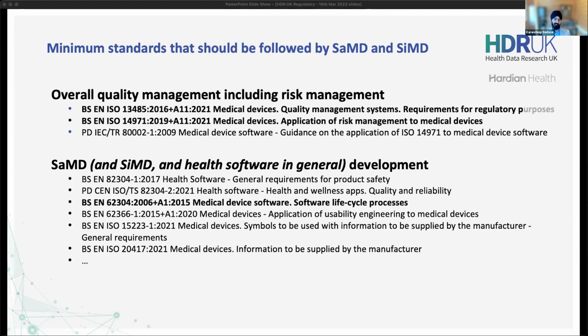So these are the minimum standards. Now, depending on what your product is, and if there's a physical element to it, and depending on what the indications are, what areas it's targeting, there may be additional standards. Now, it's important to understand standards are not mandatory. Regulations are mandatory. They're two different things, a regulation and a standard. However, standards are best practices and they often align with regulations. So it's highly recommended to use a standard. And if you're not going to use a standard, you need to have a good reason as to why that is. Next slide, Mike.